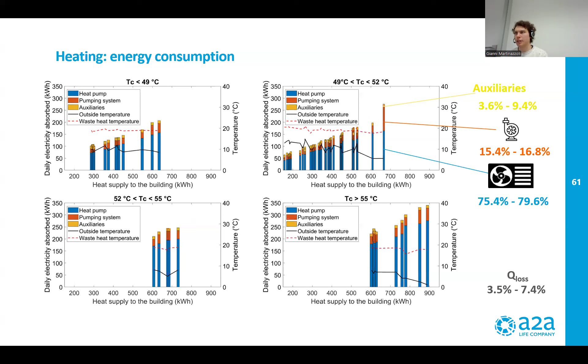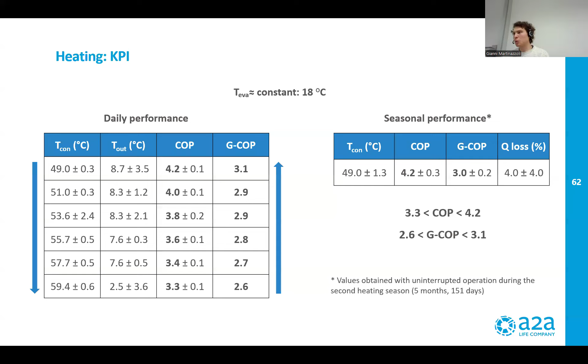We analyzed also the key performance index, in particular the COP of the heat pump and the global COP, calculated as the ratio between the heat provided to the building and the total amount of electricity consumption from the prototype. And you can see the results in terms of COP that goes from 3.3 to 4.2, and the global COP that decreased to 2.6 and 3.1.